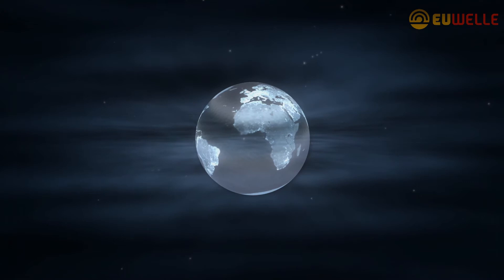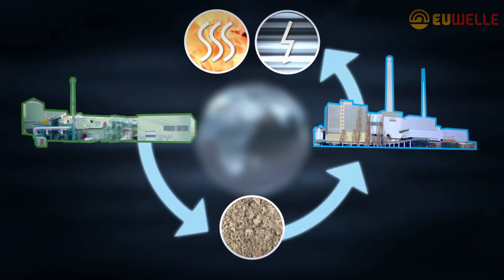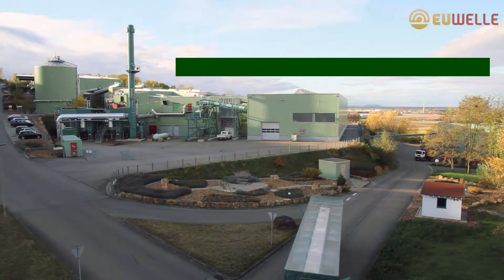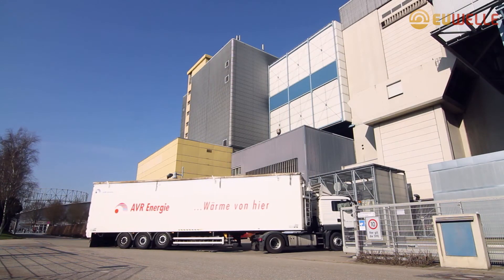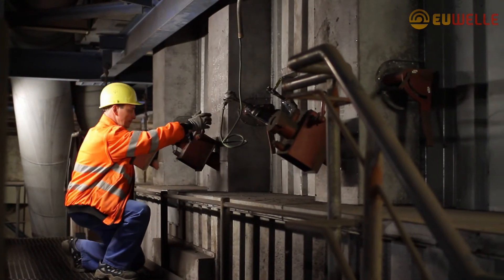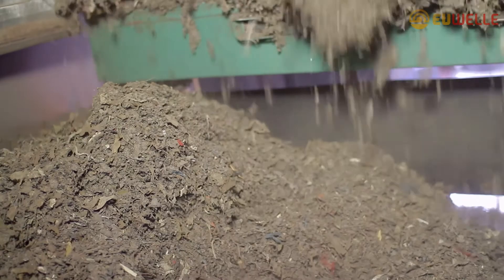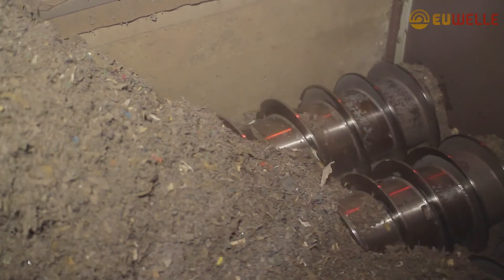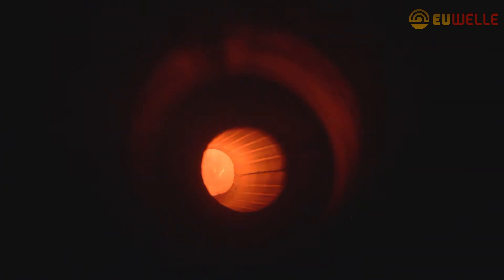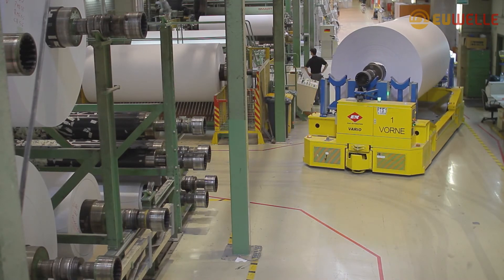What happens to the high-quality RDF created by the MBT? The energy-rich substitute fuels can then be used in industrial coal-fired power stations to generate electrical and thermal energy. In the nearby combined heat and power plant in Potsdam, Germany, up to 20,000 tons of hard coal, or about a quarter of the plant's requirements, could be replaced by substitute fuels, which equals approximately 5 megawatts. Another customer for the substitute fuel produced is a regional paper manufacturer. At the truck docking station, the material is transported via screw conveyors and conveyor chains to an intermediate silo, from where the RDF is transported pneumatically and blown into the combustion chamber of the circulating fluidized bed boiler. The household waste-sourced RDF substitutes imported natural gas, oil, or coal.